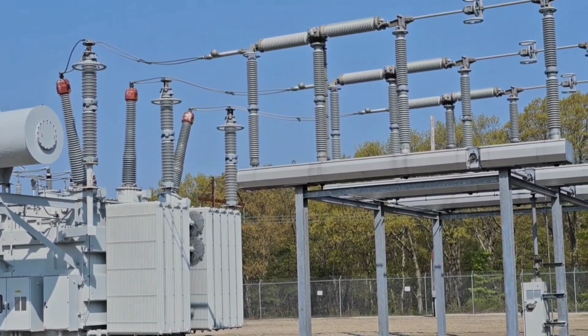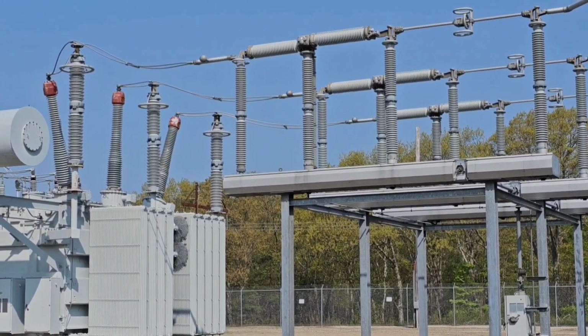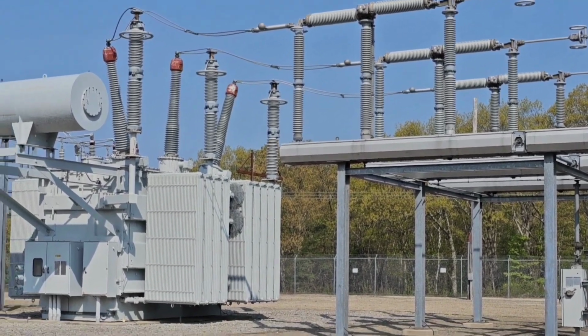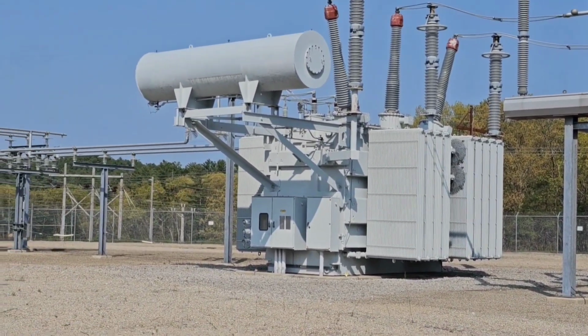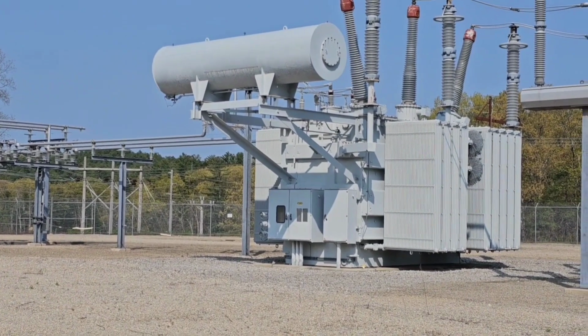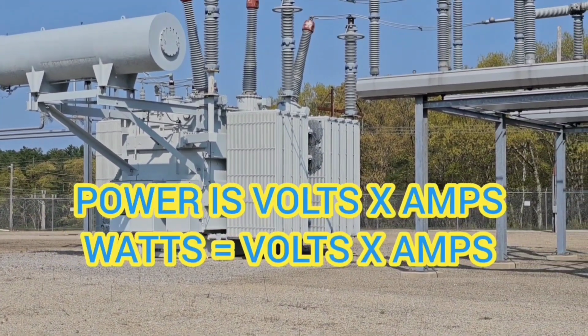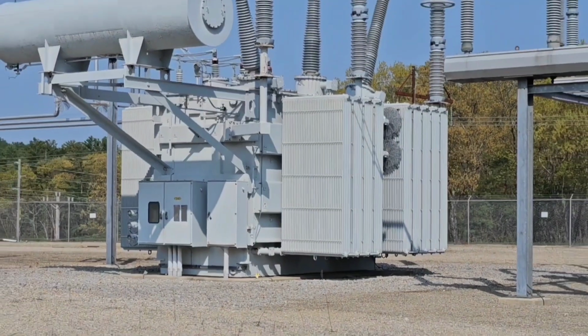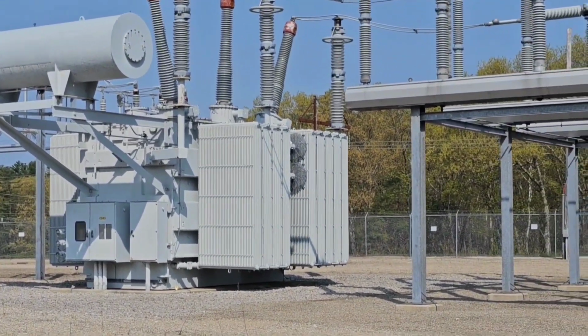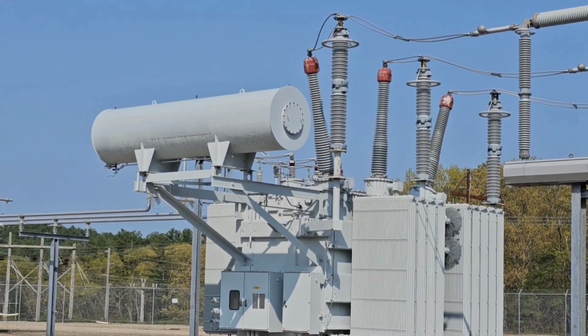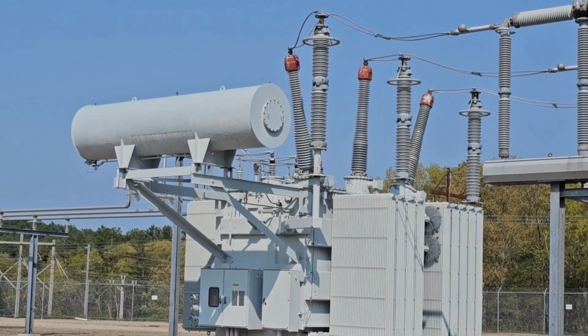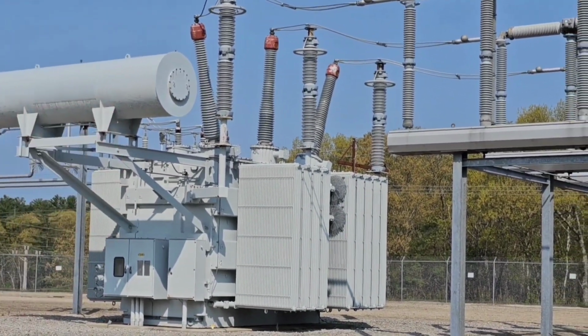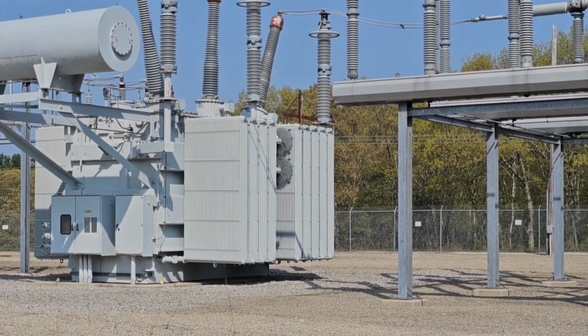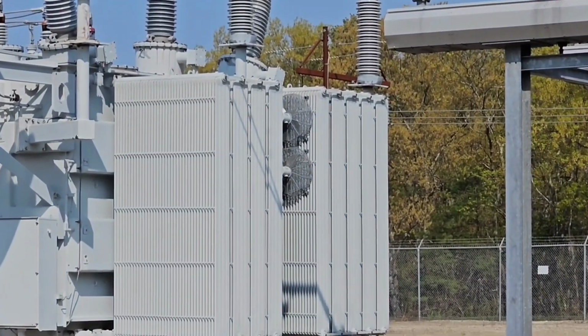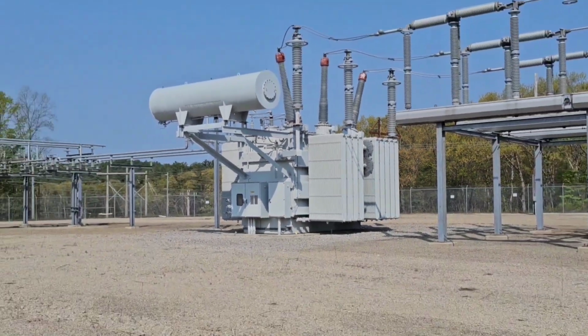So if 100 amps goes in the high side at 345,000 volts, on the low side you have 34,500 volts capable of 1,000 amps with that same amount of power. These are filled with an insulating oil so that there's not an arc inside the transformer. This thing on top of it is called a conservator, and that allows the fluid to expand and contract while the rest of this can remain totally in oil. And then the oil is circulated through these radiators and cooled with fans.